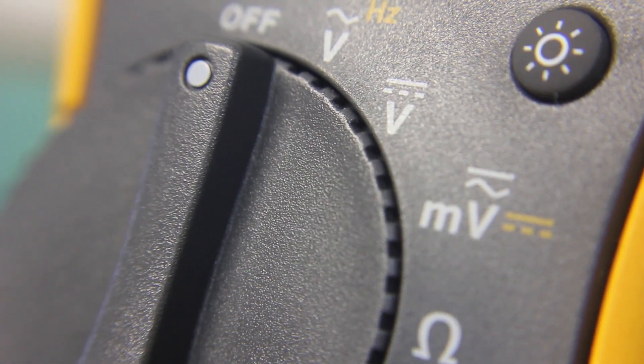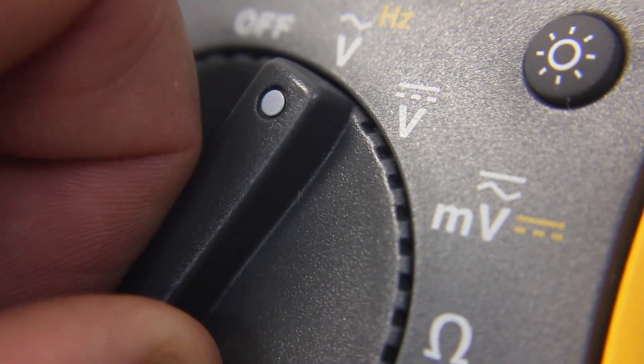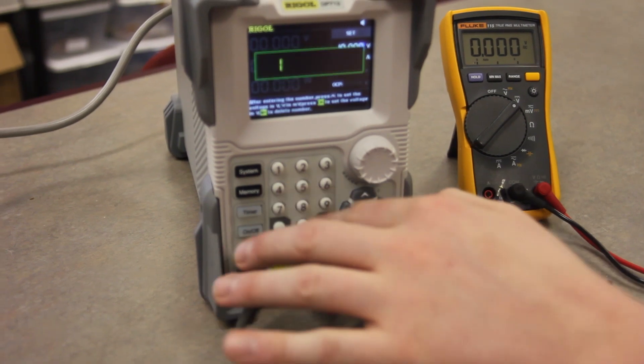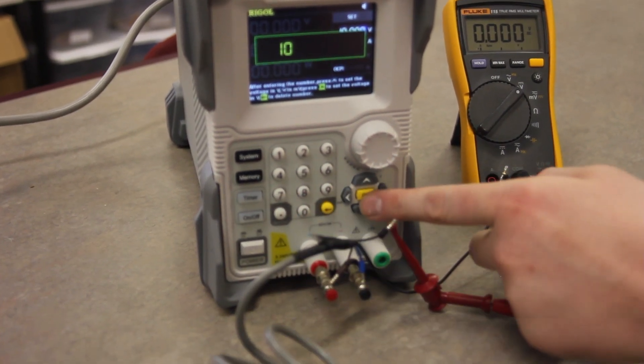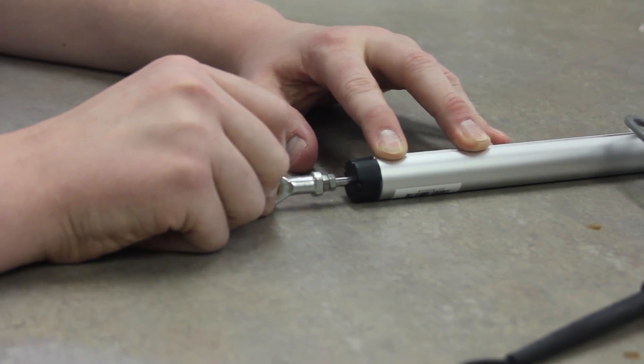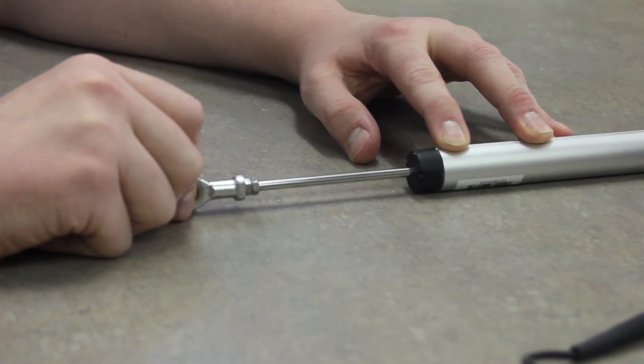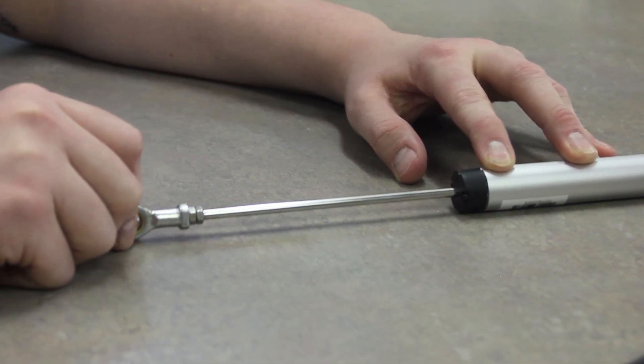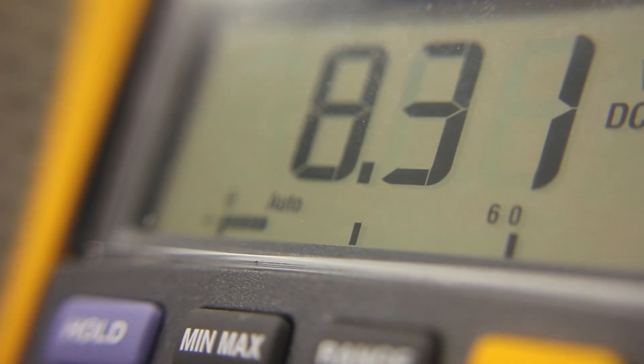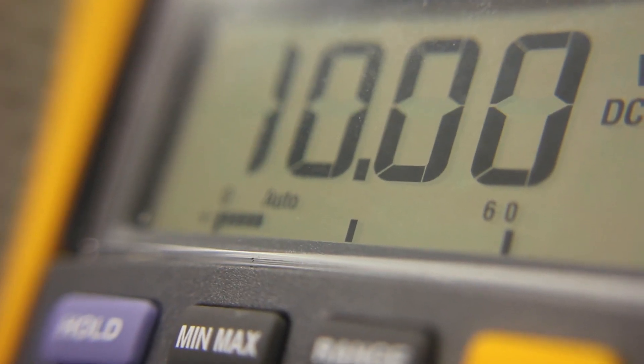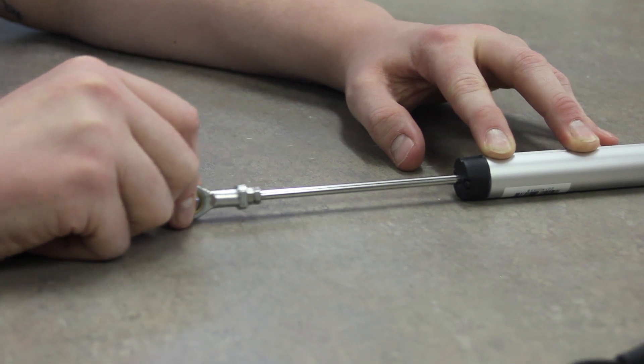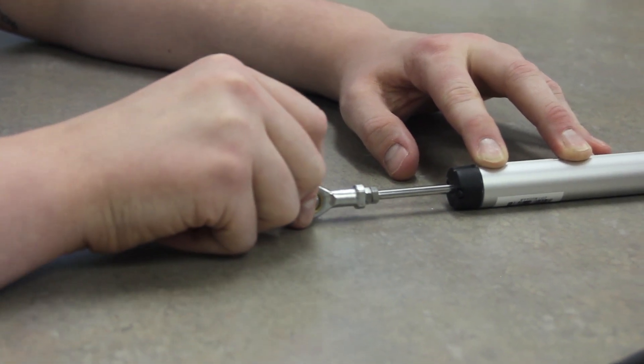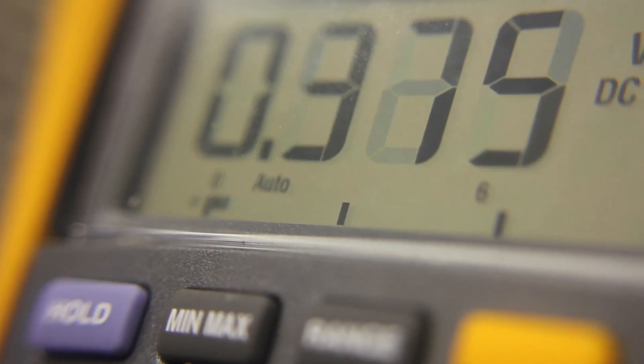Set the voltmeter to measure DC voltage. Set the DC power supply to 10 volts DC. With the linear potentiometer fully extended, the voltmeter should display 10 volts DC. With the linear potentiometer fully retracted, the voltmeter should display 0 volts DC.